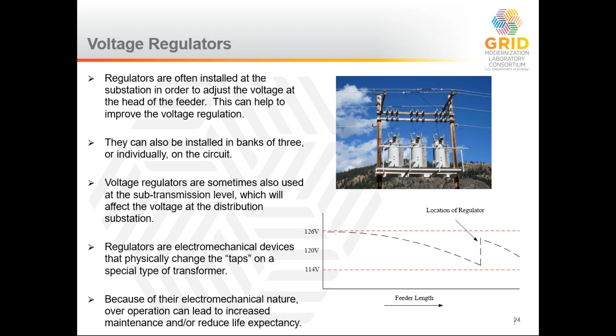Another solution for regulating voltage is what are referred to as shunt capacitors. A voltage regulator is designed to be a small transformer that actively changes the voltage up or down, typically plus or minus 16 positions. It can work in almost any location. But going back to that power triangle that we saw earlier with reactive power, we know that we primarily want to deliver active power. If you only deliver active power, or P, that will reduce the current flowing down the system. However, we know that many loads, such as motors and some power electronics, will draw reactive power.